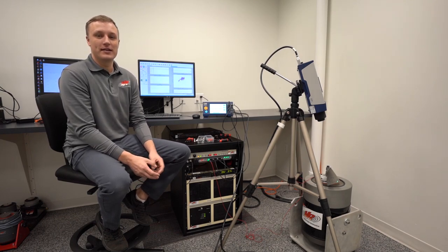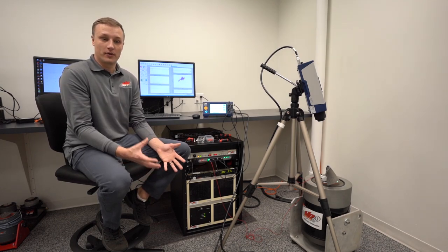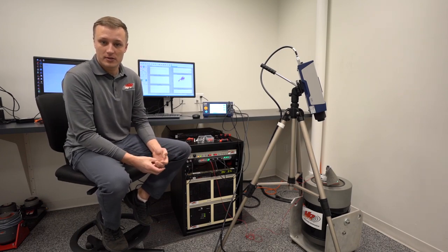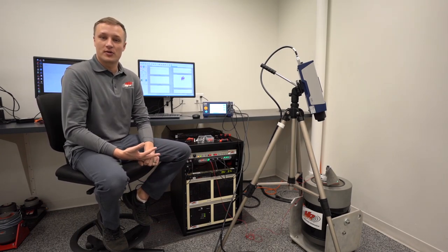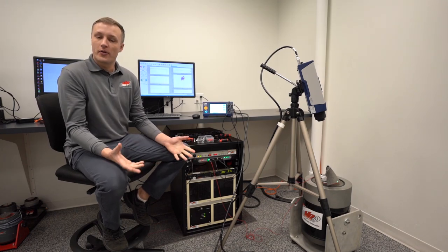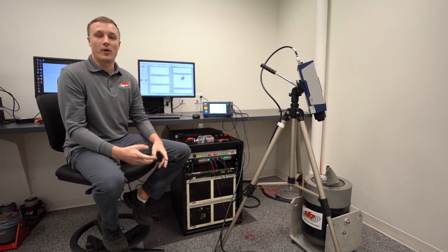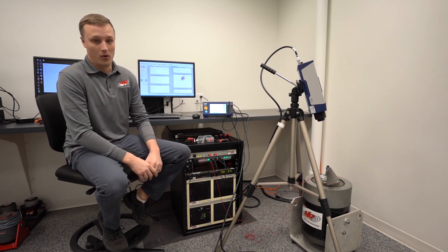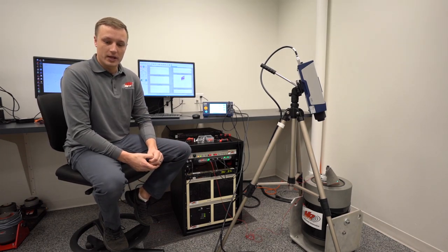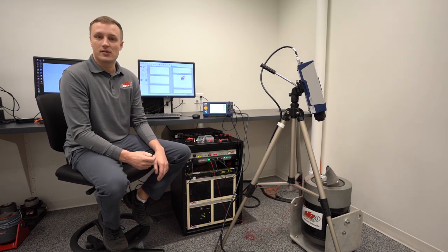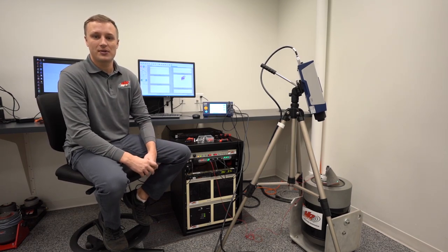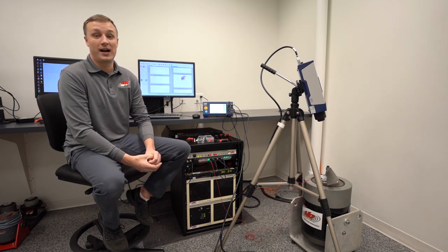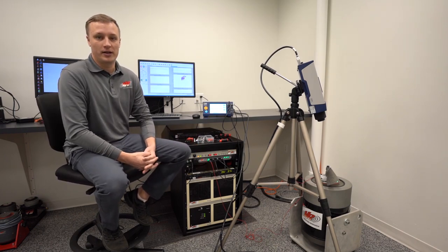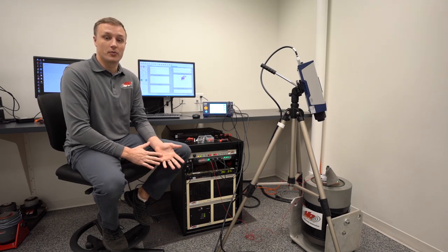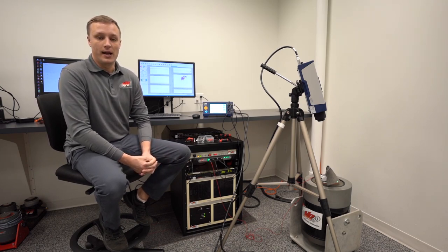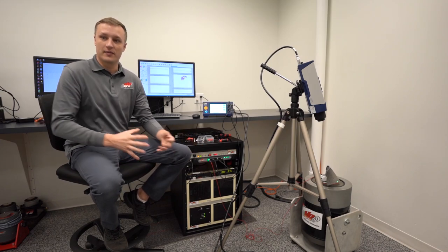We've looked at using a laser vibrometer for a variety of different sine tests and evaluations, whether that be a sine sweep or sine resonance track and dwell. Some of the other questions that we've got is, can I use this for a random test or a shock test or sine on random? And really the answer is yes in most cases. For shock type pulses, you may run into issues with the time delay in the laser vibrometer, depending on how short of a duration of a pulse you are looking at and the response of the signal.